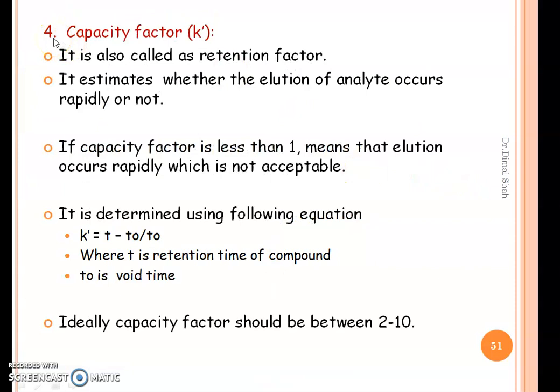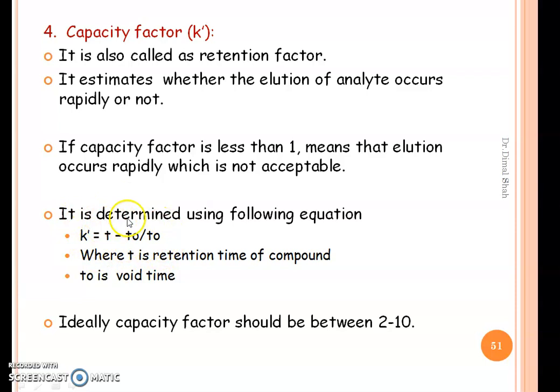The fourth parameter is capacity factor K', also called retention factor. It estimates whether elution of the analyte occurs rapidly or not. If the capacity factor is less than 1, it means elution occurs too rapidly, which is not acceptable. Capacity factor K' = (T − T₀) / T₀, where T is the retention time of the compound and T₀ is the dead time. Ideally, capacity factor should be between 2 to 10.